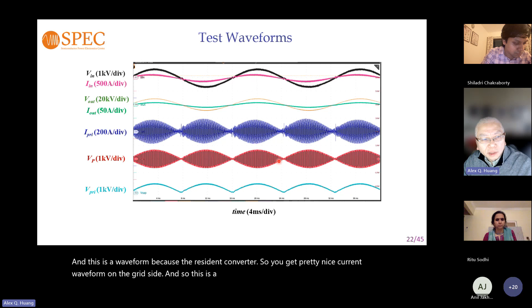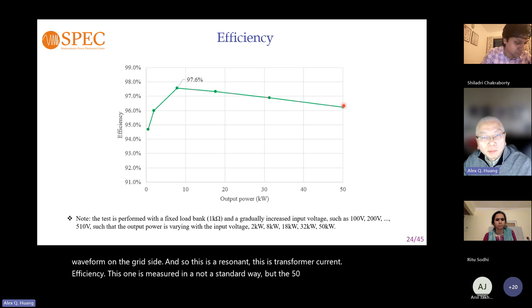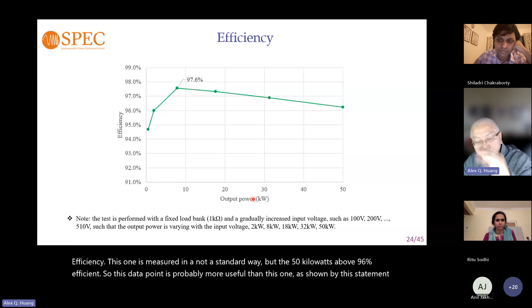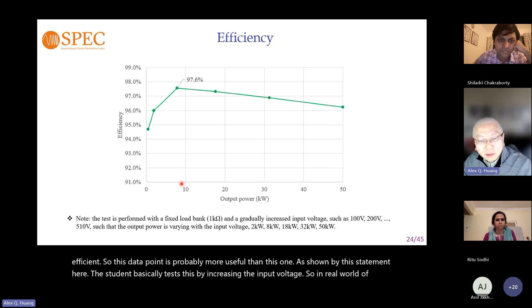Efficiency was measured in a non-standard way, but the 50 kilowatt point is about 96% efficient, so that data point is probably more useful than this one. The student basically tested this by increasing the input voltage, but in the real world you should not test this way — you should change the load, not the voltage.